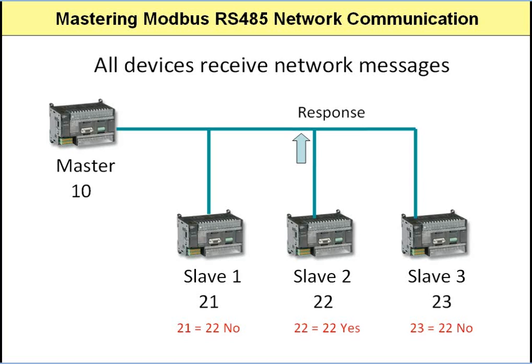So this is why each device on a Modbus network needs to have a Modbus Unit ID. The master on the network depends on it in order to single out any device to communicate with. This is one of the most important concepts in understanding Modbus. It is also very important to remember when we begin our look at RS-485 later down in the course.